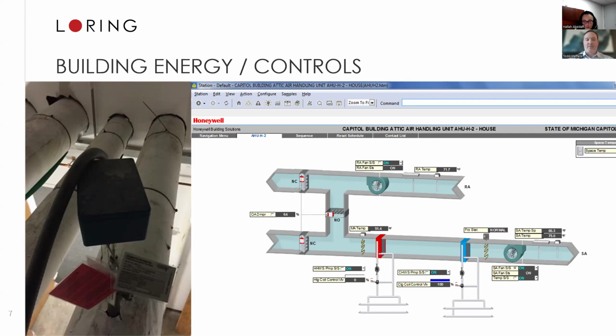And that's one thing a retrocommissioning process can do, is when you go into an existing building, look at the actual points in the field versus what you're seeing on your head-end computer. So this photo on the left is part of a retrocommissioning project we did, where this is a chilled water flow meter. It's a turbine type, but you can see that it is turned a little bit at an angle to the pipe. And this type of sensor needs to be installed perfectly parallel to the pipe to get a good reading, because then the paddle sensor inside the pipe is actually perpendicular to the direction of flow.